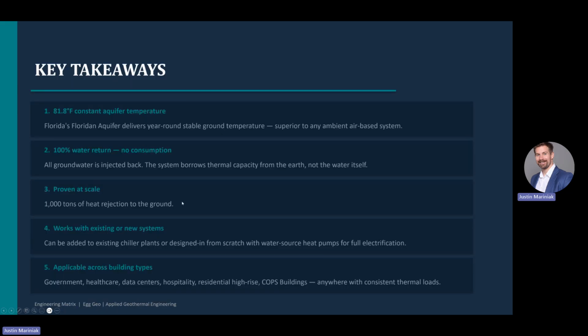The key takeaways. Our aquifer is a consistent temperature year-round at 82 degrees. These systems do not consume any water. All the water is returned to the aquifer. These systems can handle almost any size heating and cooling load. They can be designed for new construction or retrofitted on existing systems. They work for any building type, even special cases like critical facilities.